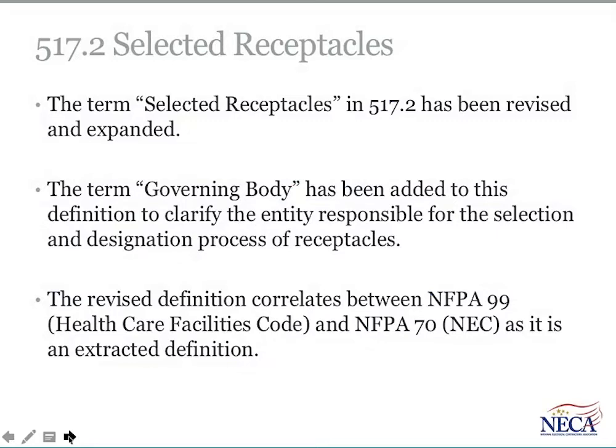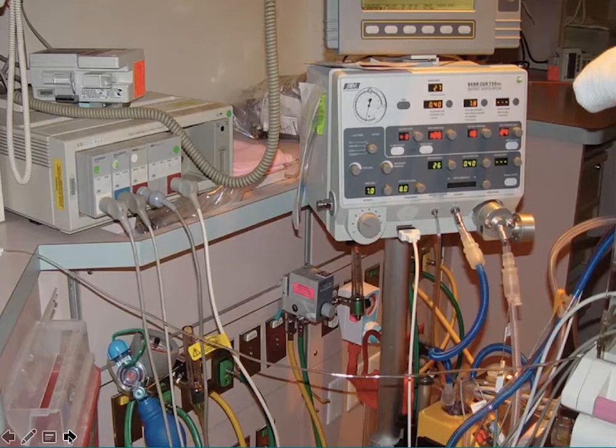And another change, dealing with selected receptacles, is in 517.2 to clarify who's doing the selecting. Now we have this definition of governing body of the healthcare facility, and the definition of selected receptacles now includes the phrase governing body. It really clarifies who's doing the selecting of the types of receptacles necessary for those spaces. That's a good clarification. Here's an example of a critical care location with life support equipment hooked up to patients, and there would be a number of selected receptacles from the various branches, the normal branch, the equipment branch, and the critical branch, that would be selected for those locations.